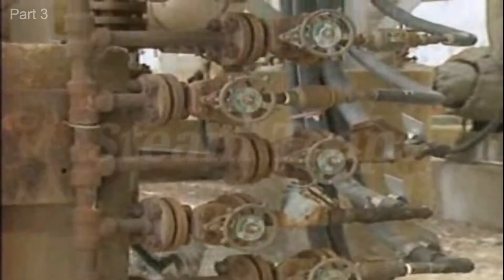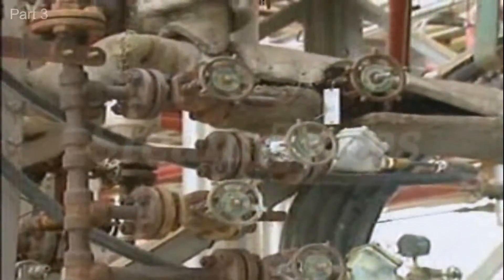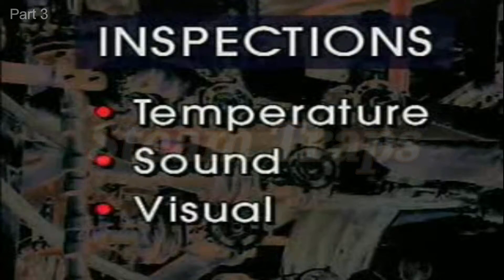After a steam trap station has been surveyed or inspected, the next step is to survey the individual traps in the station. Trap problems aren't always easy to detect, so a combination of different inspection methods may be used. Typically, a thorough trap survey combines information obtained by performing three types of inspections: temperature, sound, and visual.